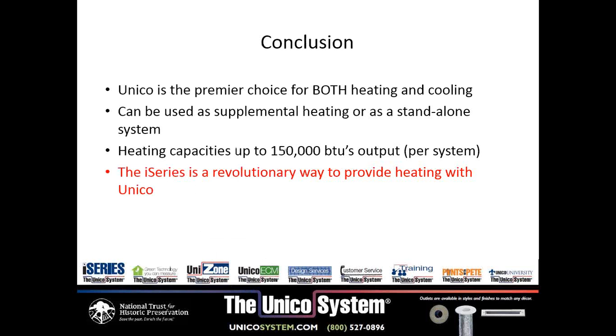And, of course, the I-Series is something you're going to be hearing more and more about. We're going to feature this at the ASHRAE show in Chicago. This has been out for about 5 or 6 months. It is a 1-ton, 2-ton, and 3-ton heat pump system that uses inverter technology. In other words, inverter technology just supplies the right amount of heating or cooling based upon what the load is. So unlike a heat pump that we normally sell that's either on or off, this is fluctuating based upon the load. So that's our performance here on heating.